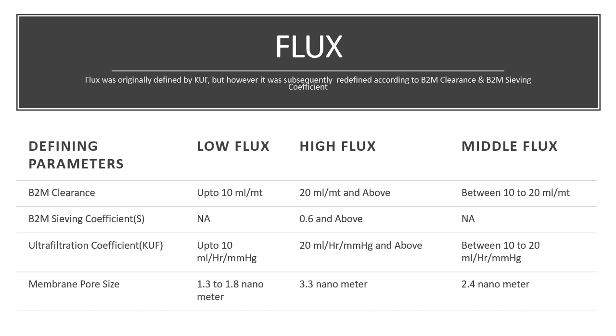Based on these parameters, dialyzers are categorized into three groups. Low flux dialyzers have a beta-2 microglobulin clearance up to 10 ml per minute. The beta-2 microglobulin sieving coefficient is not applicable for low flux because theoretically these filters cannot remove beta-2 microglobulin due to its higher molecular weight of 11,800 daltons. Low flux dialyzers have a KUF up to 10 ml/hr/mmHg and a pore size of approximately 1.3 to 1.8 nanometers.